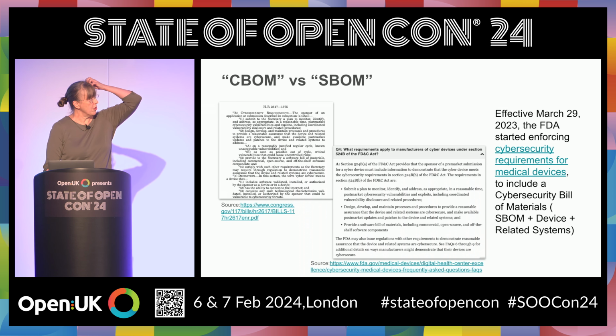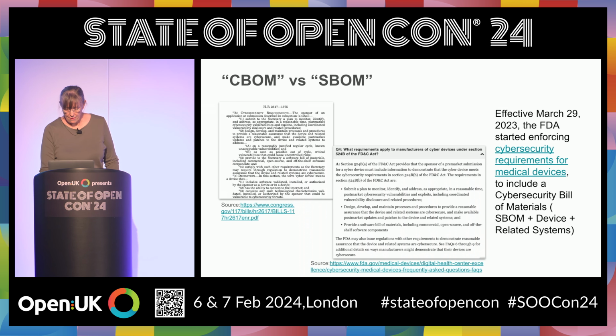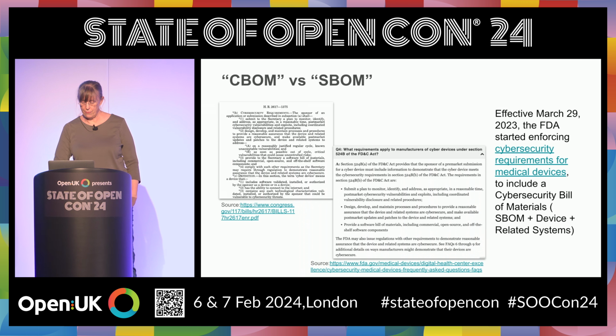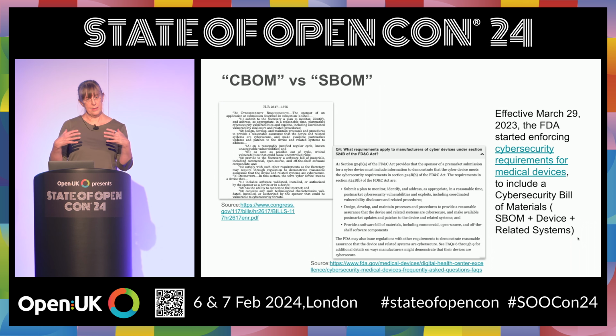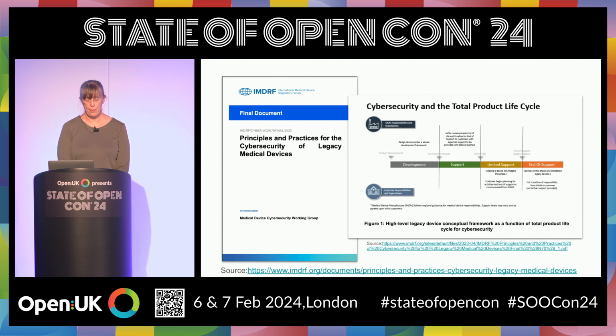The other thing that's been emerging is the FDA last year started enforcing the cybersecurity requirements for medical devices. This sometimes gets referred to as a CBOM, but it pretty much is an SBOM. However, they are starting to look for device and related systems. So it's starting to bring in the hardware aspect that hasn't been there. Okay? And so that's what they're looking for. They're also looking for aspects of support.